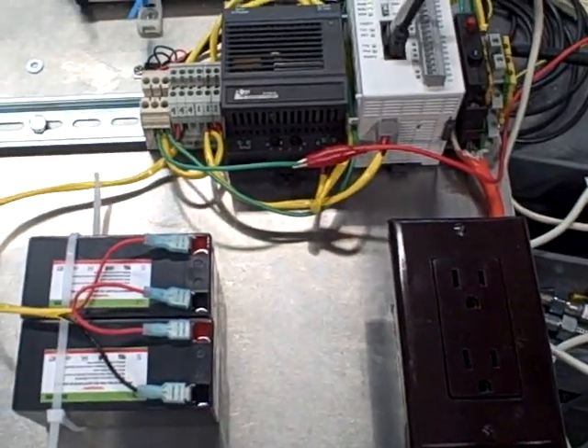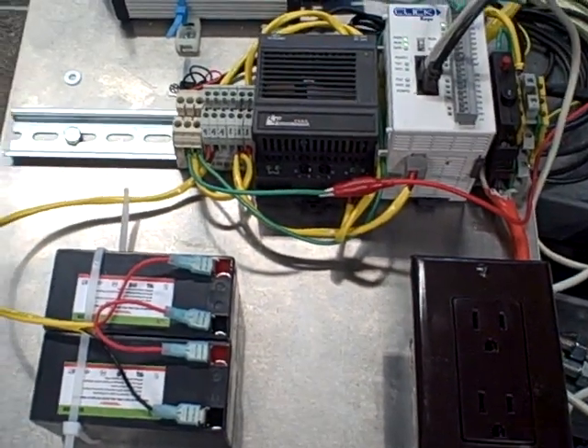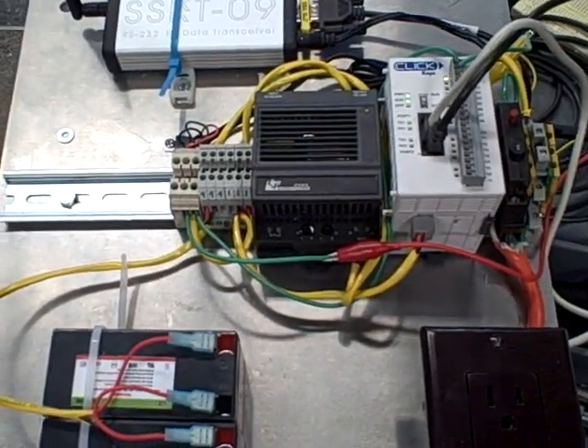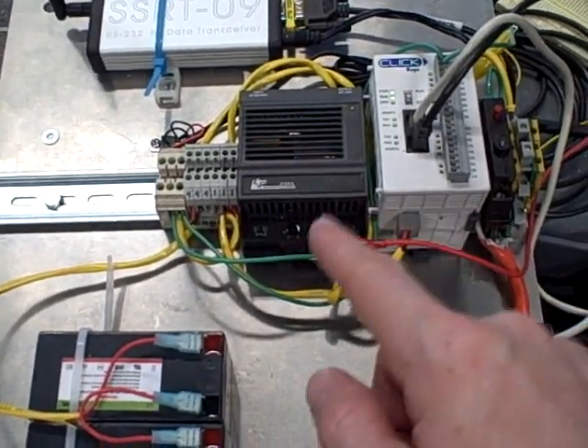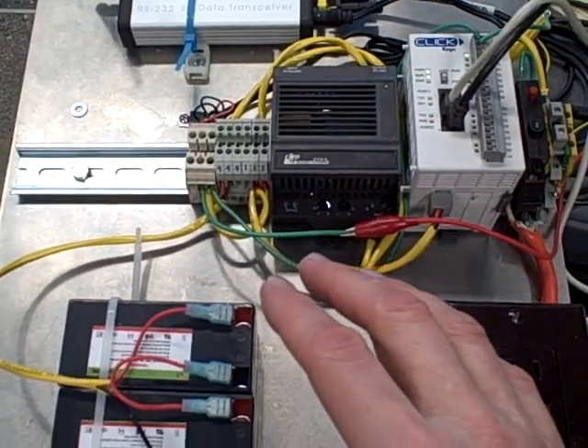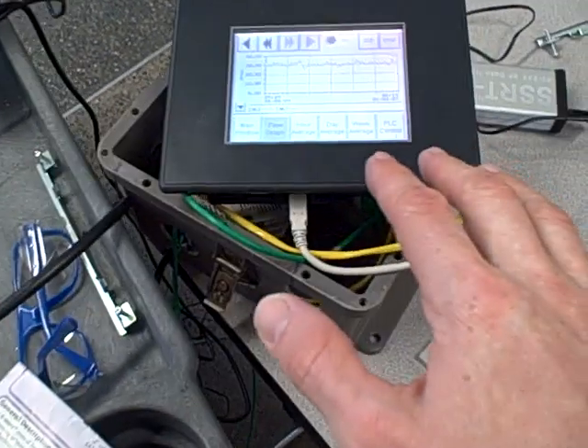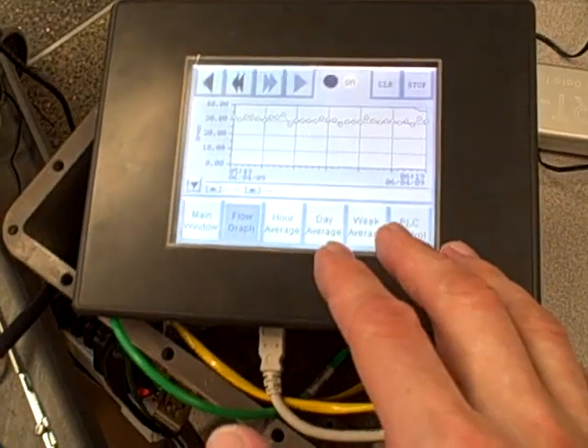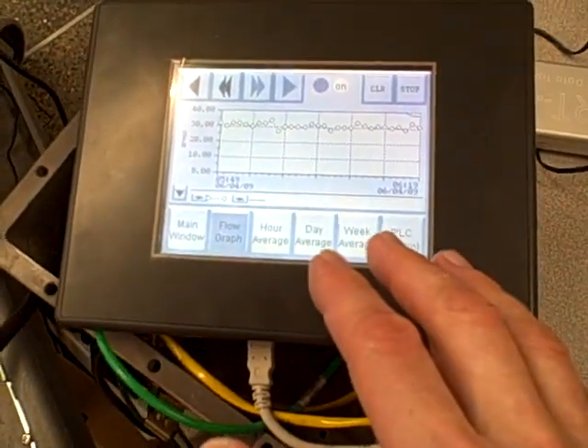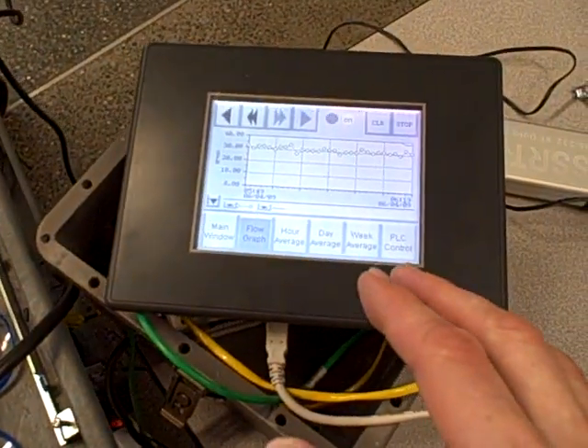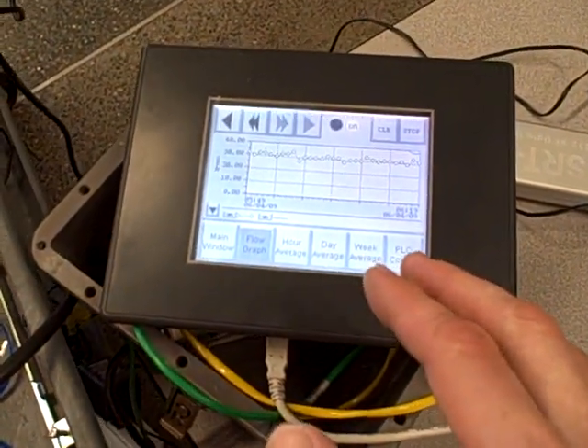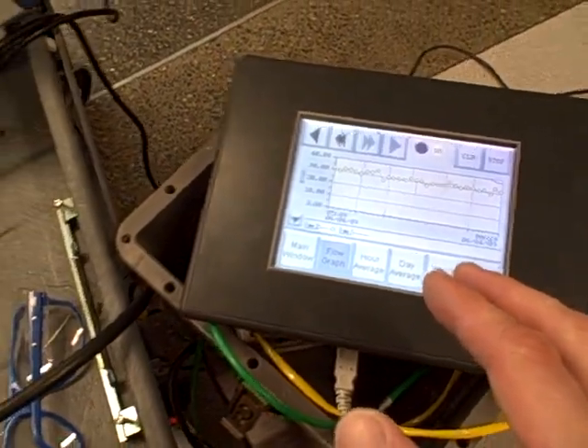One thing I have not described about the system yet, but it's critically important, is the radio link. The way the system is built, the PLC and the flow meter are in a remote location, and the main HMI is going to be in their maintenance shop, which is about a thousand feet away. There's no way for us to practically run wires between the two locations, so we are using a spread spectrum serial data link to do the job.